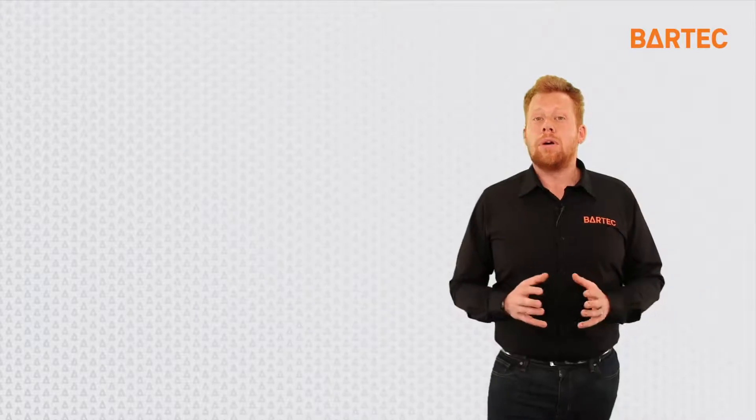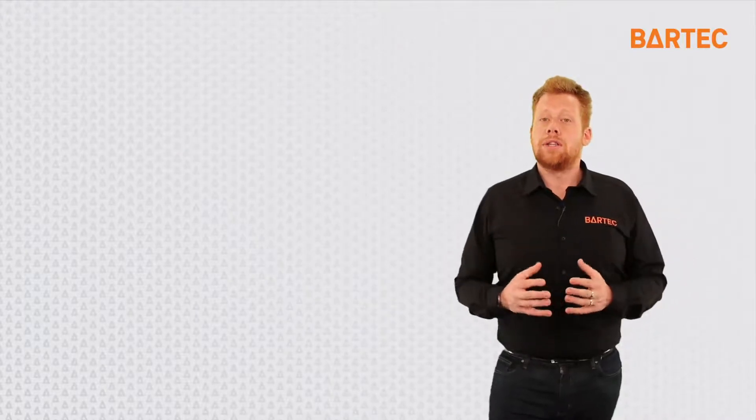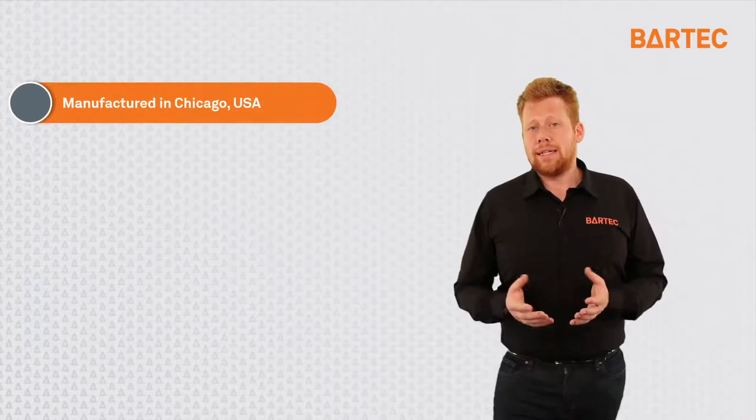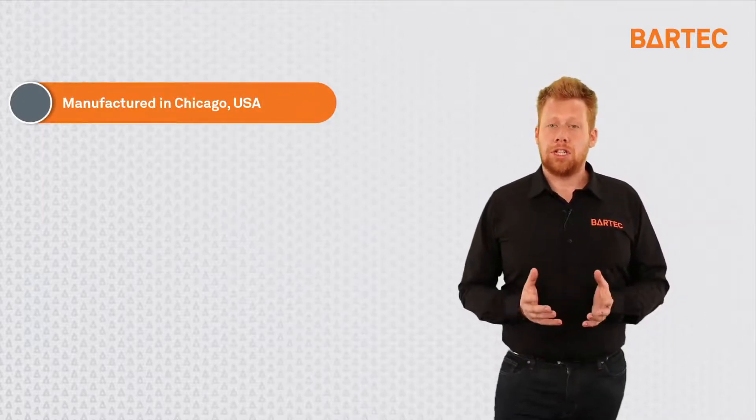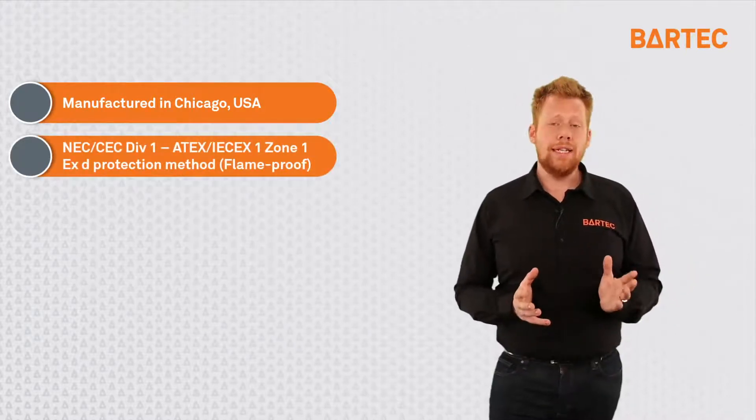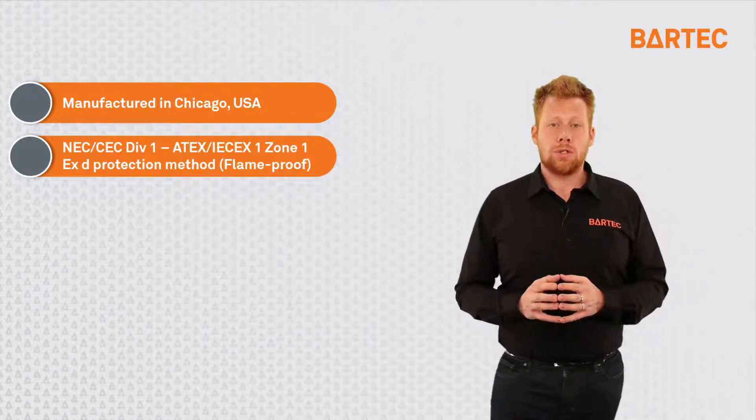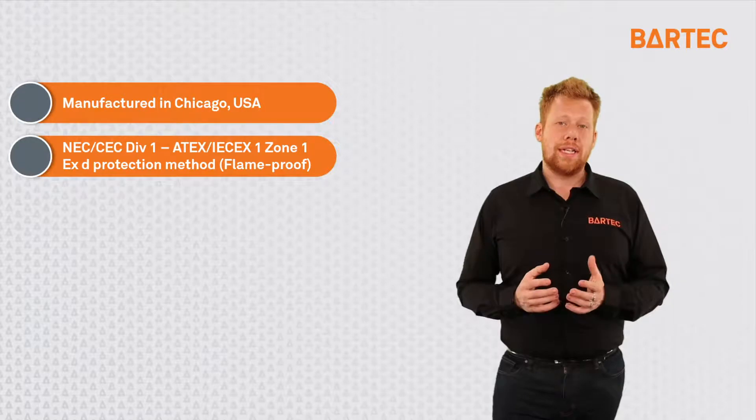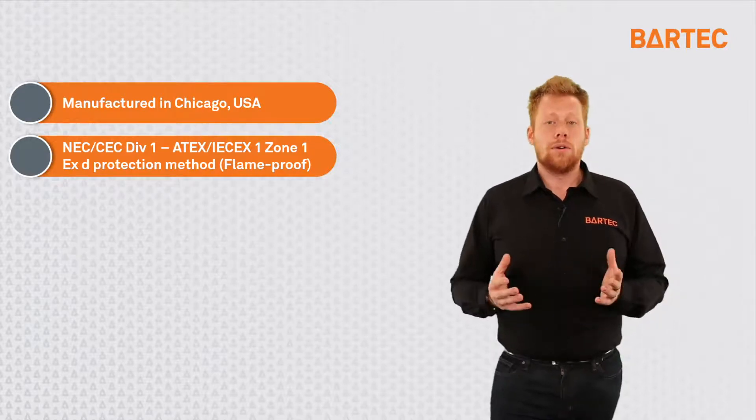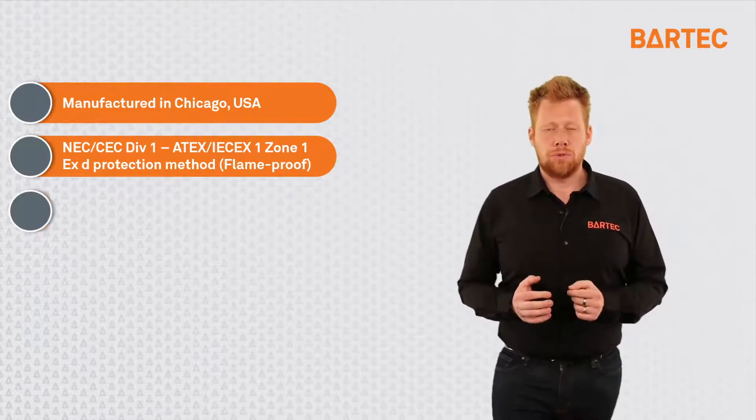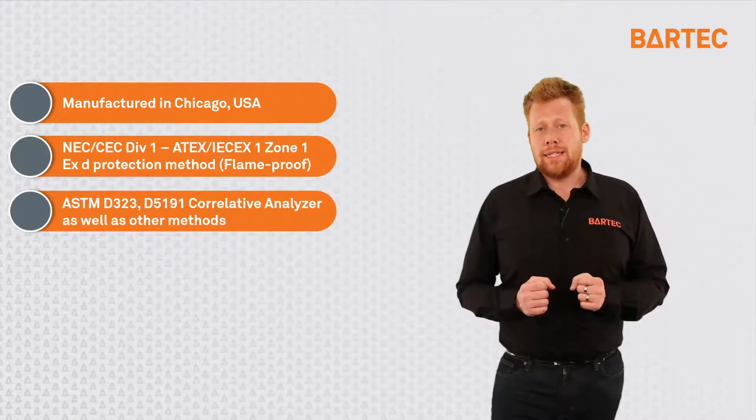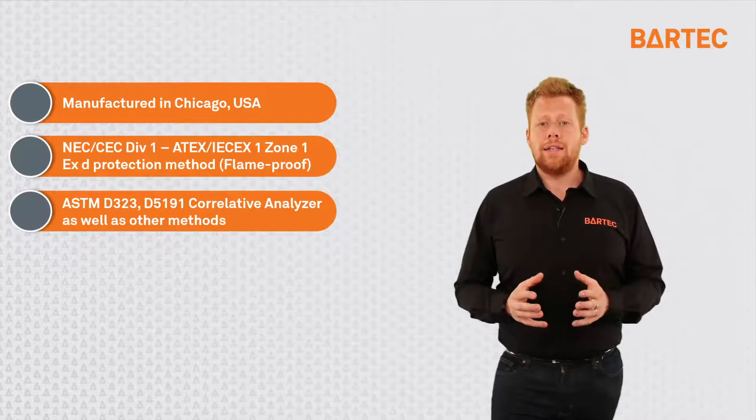Now that you know how the P700 measures RVP, there are a few more features I want to point out. The first one is that this analyzer is manufactured at our Bartec Orb factory in Chicago in the US. The system is rated for NEC CEC Division 1 and ATEX IEC EX Zone 1. To do so, we use an EXD protection method, flame proof, also commonly called explosion proof.